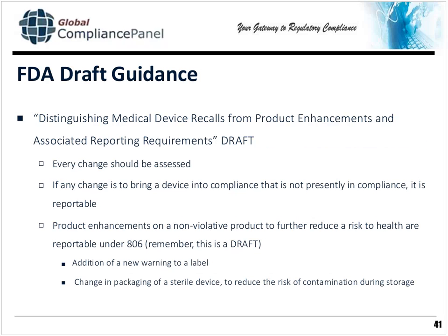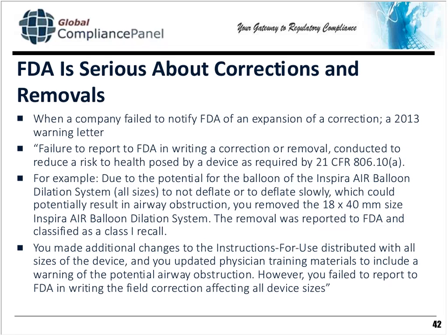There is a device draft guidance, and product enhancements on a non-violative product to further reduce the risk to health are reportable. Addition of a new warning, a change in packaging of a sterile device, etc. So improvements may very well be reportable. And FDA is serious about these. There was a 2013 warning letter: you made changes to the instruction for use, and you updated the physician training materials, but you failed to report to FDA in writing the field correction affecting all device sizes. So this is just as serious a problem with FDA.